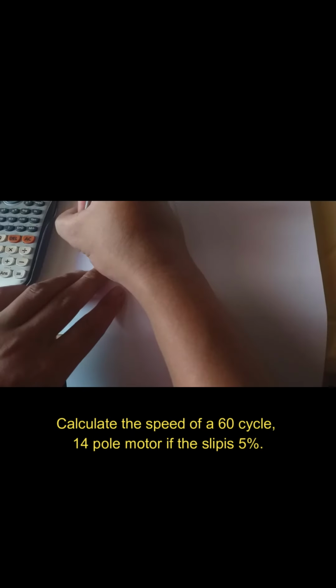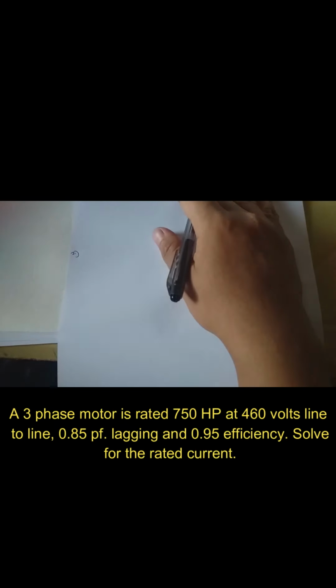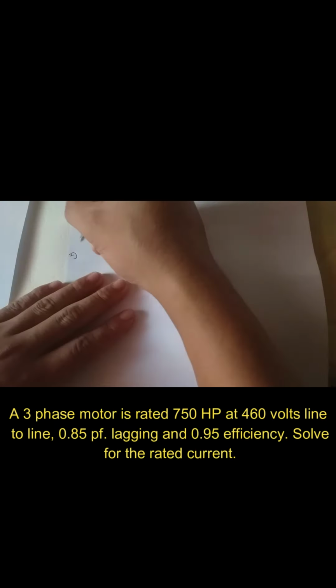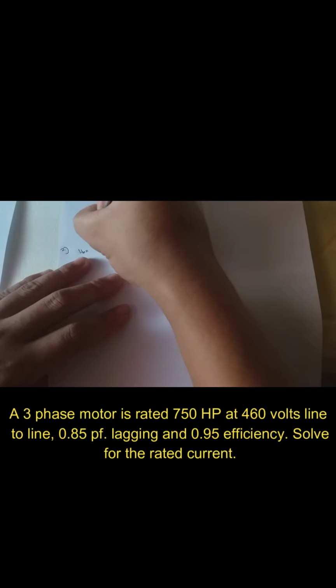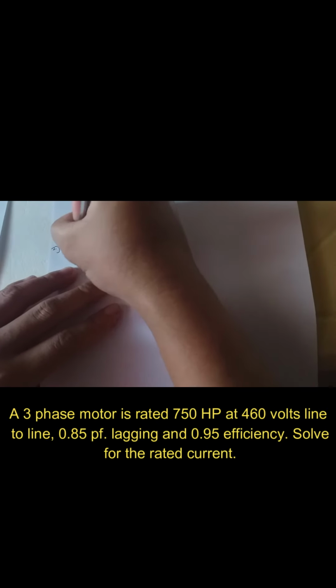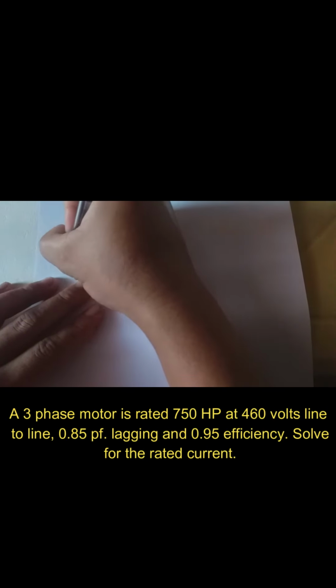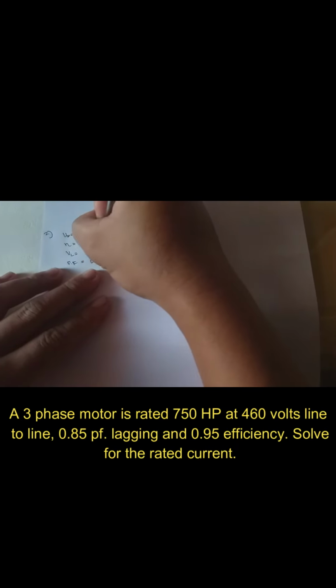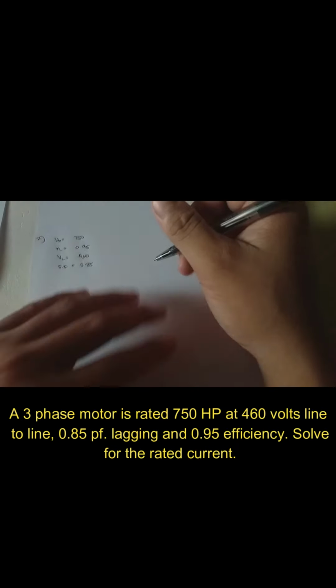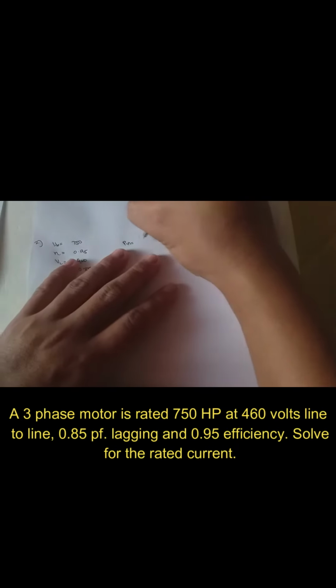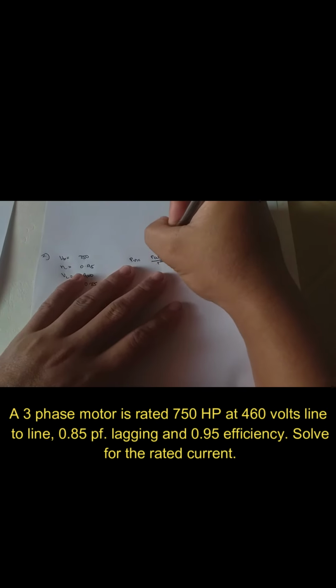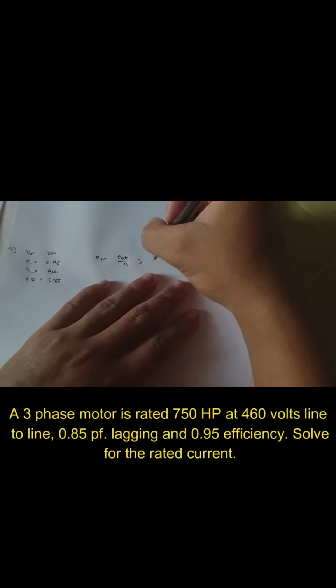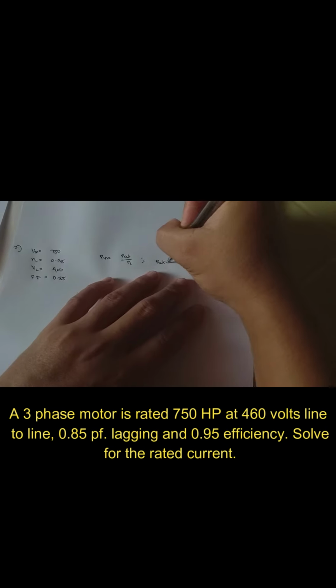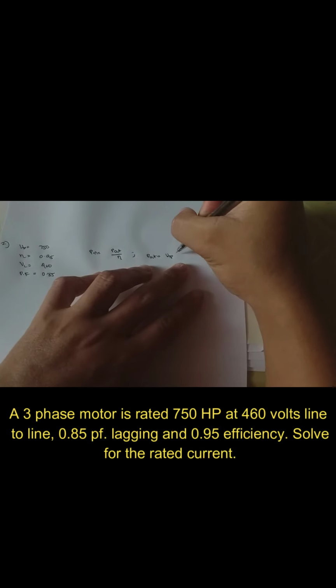So we proceed to question number 2. We have data of horsepower of 750, efficiency of 0.95, load voltage of 460, power factor of 0.85. First, compute the input power. But we don't have output power, so first we will compute the output power.